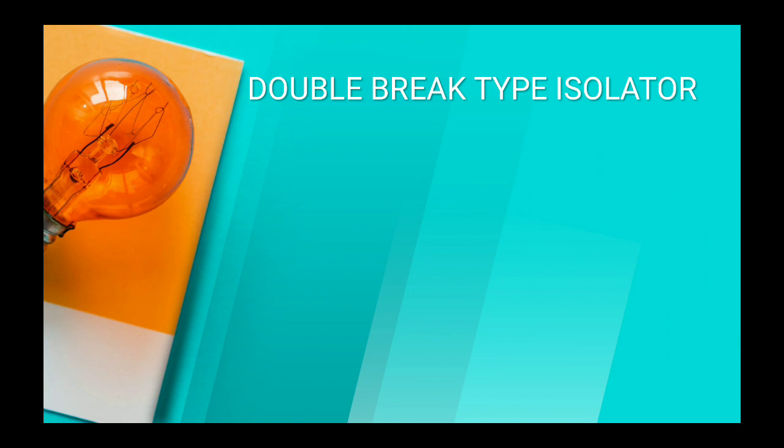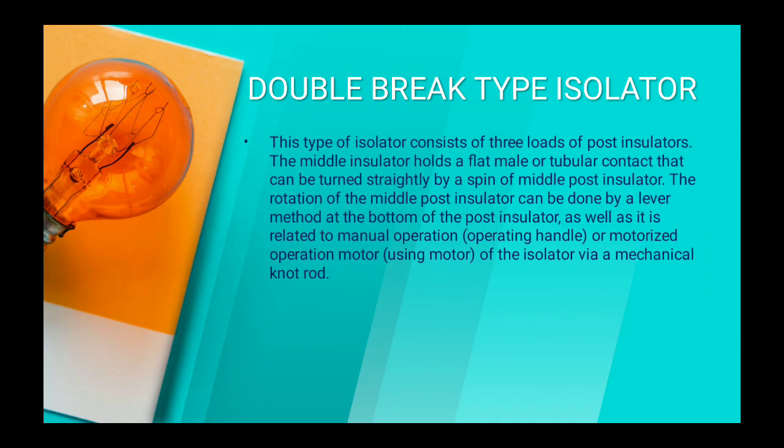Double break type isolator. This type of isolator consists of three sets of post insulators. The middle insulator holds a flat male or tubular contact that can be turned by rotation of the middle post insulator. The rotation of the middle post insulator is done by a lever method at the bottom, and it is related to manual operation or motorized operation of the isolator via a mechanical rod.